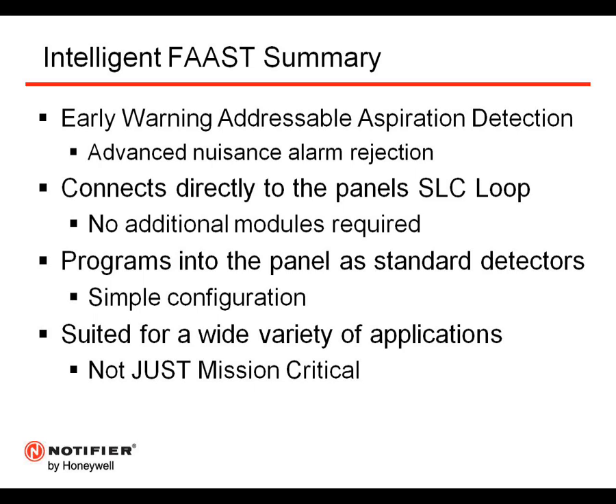So if we think about this as some of the other slides that we saw earlier, using conventional aspiration or using a competitive SLC or competitive high-level interface integration, this does not require any additional modules, so you don't have modules to purchase, to install, again, to wire, to configure, and again, to potentially troubleshoot. The only thing we're going to need for Intelligent FAAST is going to be our SLC connection, and then either a 24 volts DC power connection either coming from the panel or from a separate UL864 listed power supply.